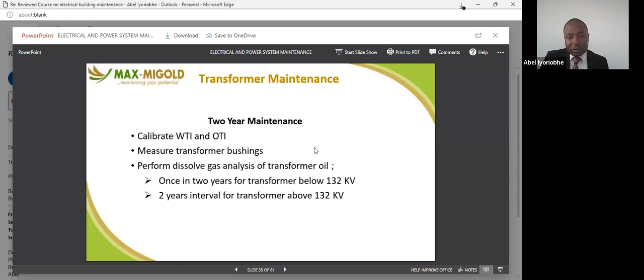You measure transformer bushings, again you can see the importance of bushings. Perform dissolved gas analysis of transformer oil. So it will give you, just like in chemistry, you want to test the strength of oil. These are what you use to know whether the oil is still capable of sustaining that transformer. So you do this once every 2 years for transformers, and so on.